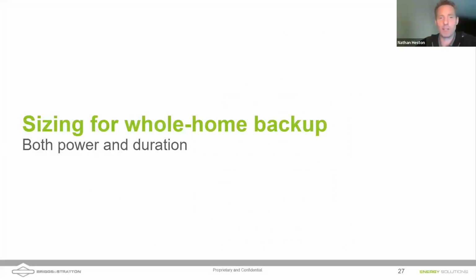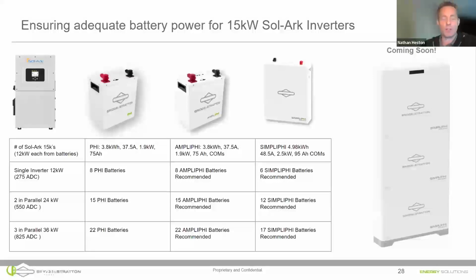So let's talk a little bit about sizing. We'll get into more details here. I just want to point out that it's important to size your batteries to the power of your inverter. We all know about the energy capacity of the batteries and how long those batteries will last, and working with the customers to size their battery system to their needs. But we also have to size to the needs of the inverter in a high power situation, right? So the Sol-Ark 15K can pull 12 kilowatts from the batteries. If you have non-communicating batteries, you need to make sure that you're programming in the power output ability of your batteries into the inverter. And you do that by programming in the maximum current.